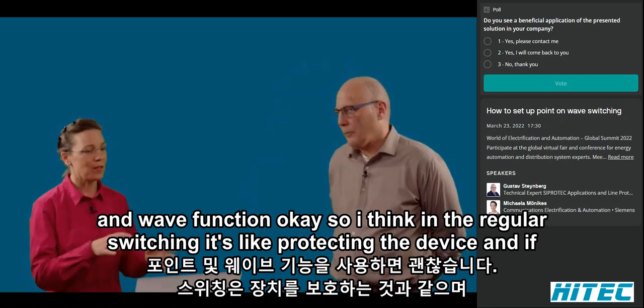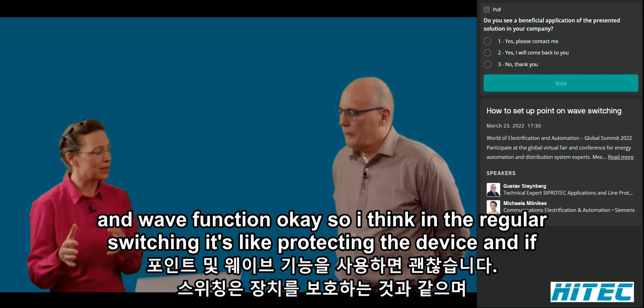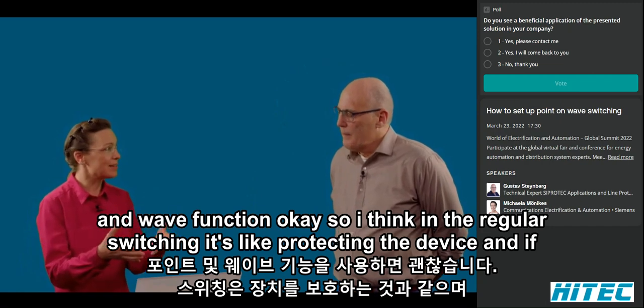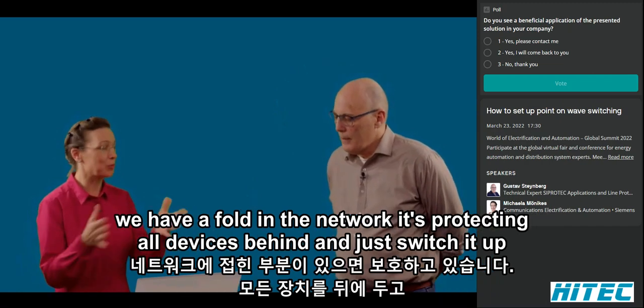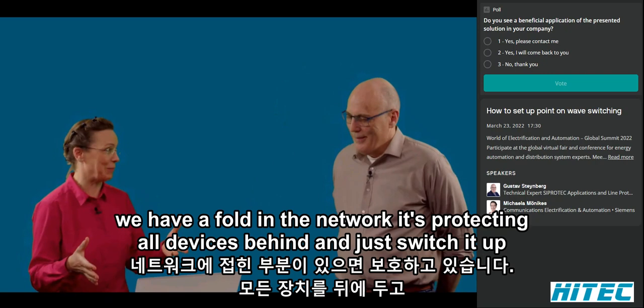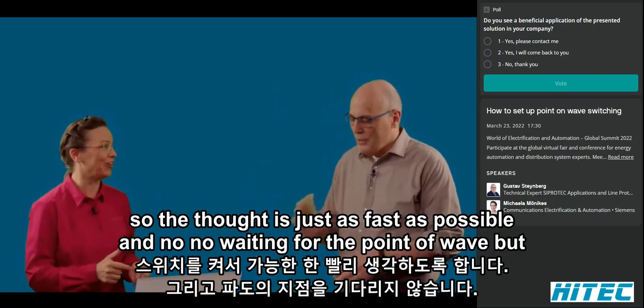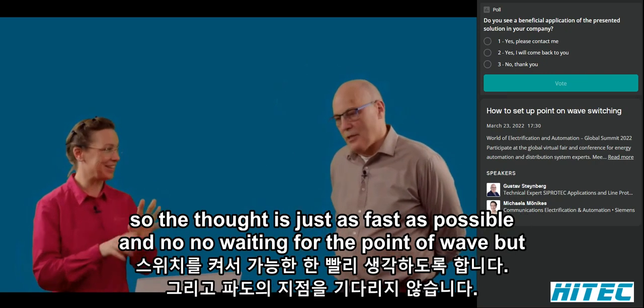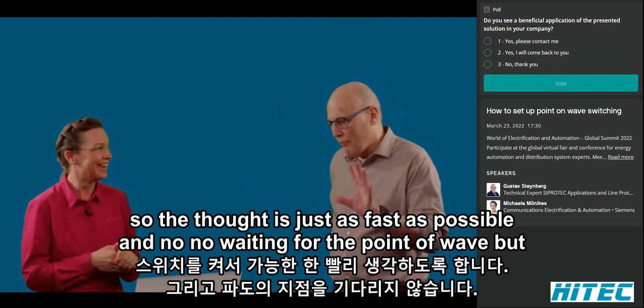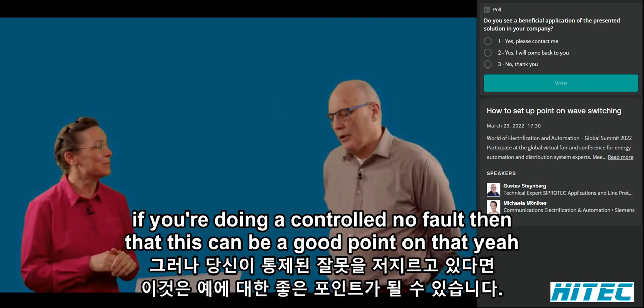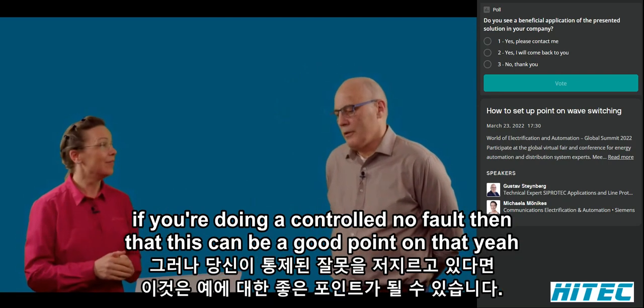Okay. So I think in the regular switching, it's like protecting the device. And if we have a fault in the network, it's protecting all devices behind and just switching it off. So the fault is just as fast as possible, with no waiting for the point-on-wave. But if you're doing a controlled no-fault switching, then it can be with point-on-wave.